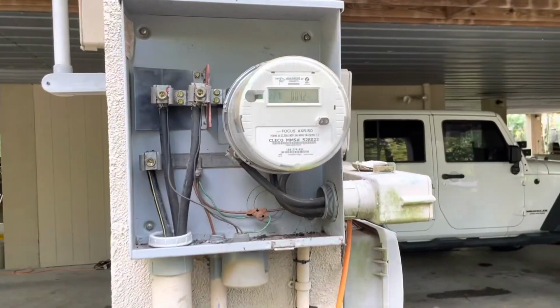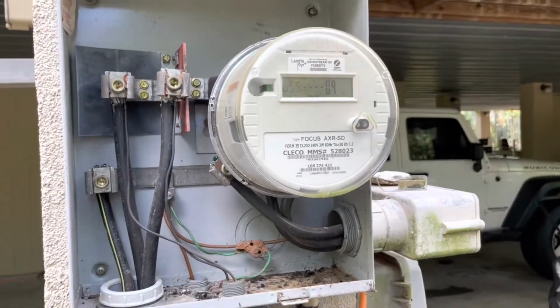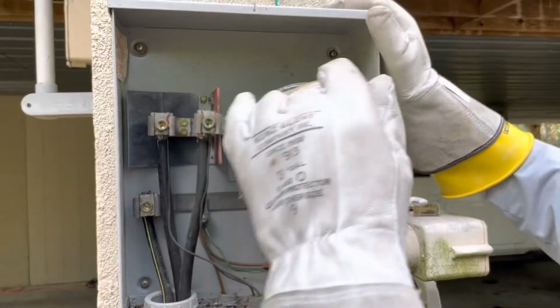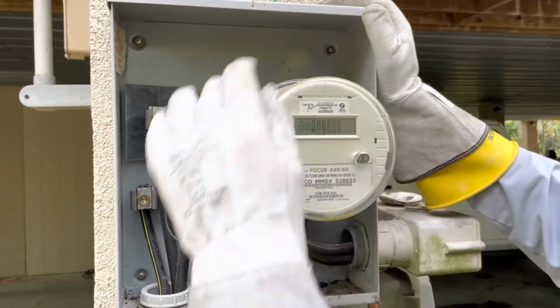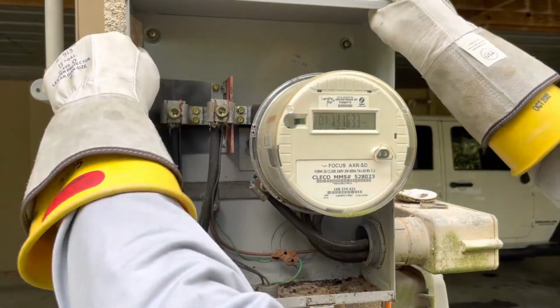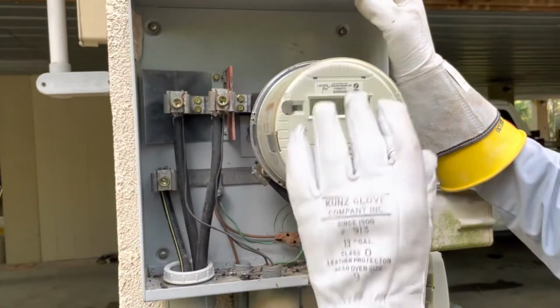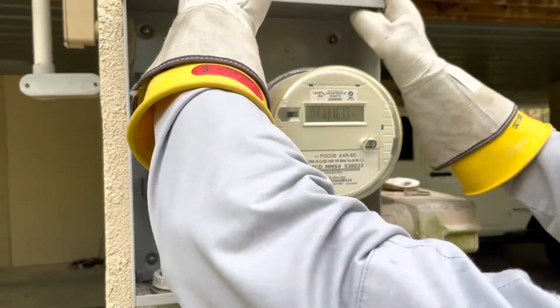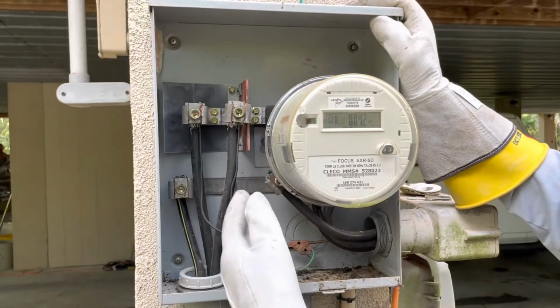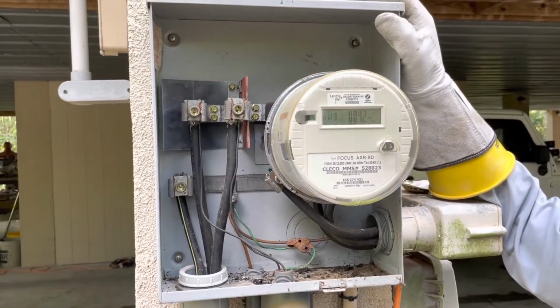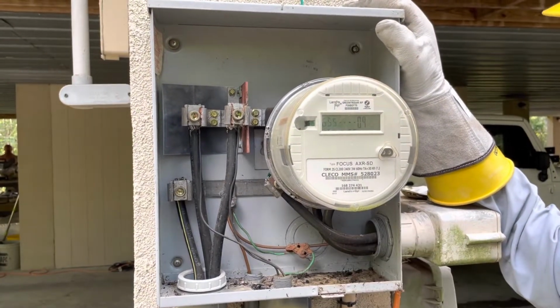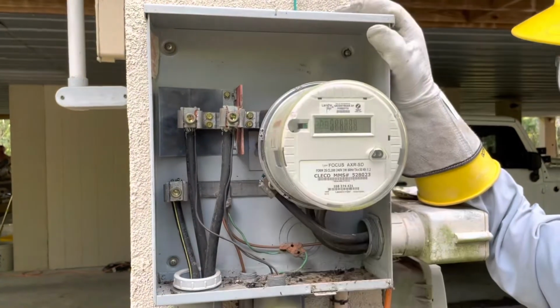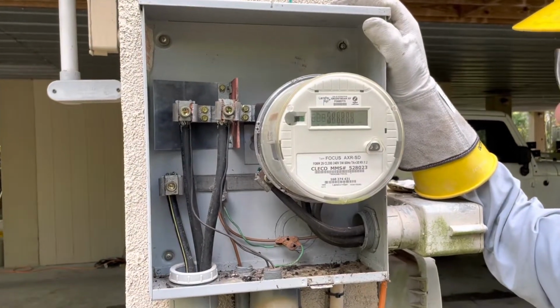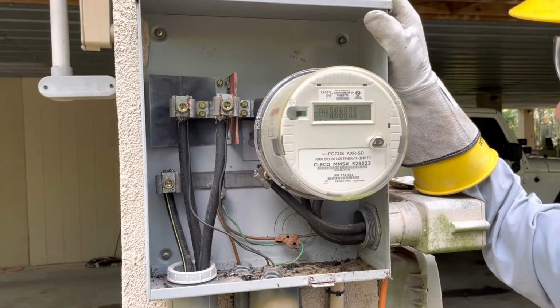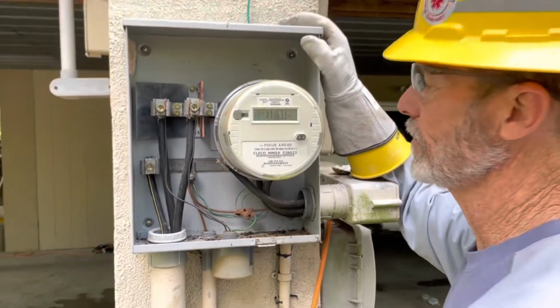What I'm looking for when I get into this meter pan is to make sure the condition of all my lugs is good and that the pan is actually connected to the building. When you go to pull this meter, you don't want this all loose or any lugs loose, because then it could become a hazard where you're stuck standing right here holding the meter with the lugs that just broke off the back of it. That's why it's important to carry your cell phone with you, because we work most of the time by ourselves.